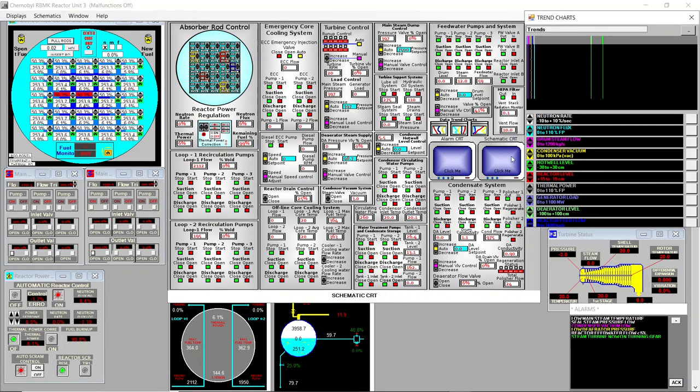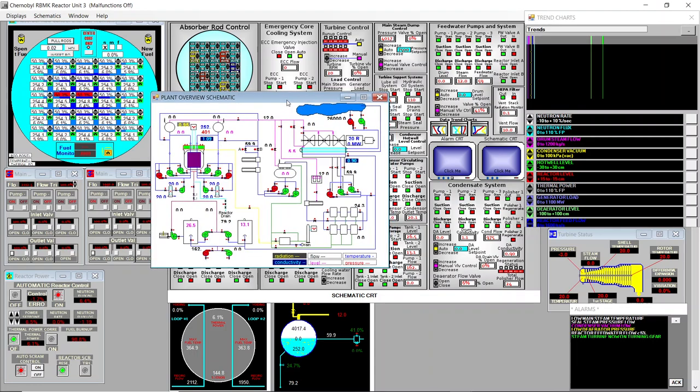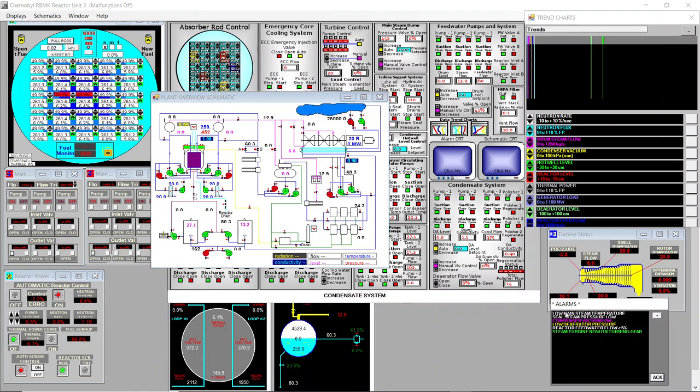a disk rupture. What is a disk rupture? Actually, if you don't patch the ICD file, it causes a disk rupture. You start the simulation with the ruptured disk. This is a mechanical device which is placed between the condenser and the feed water pumps. I don't know exactly where, but it's within this path here. It breaks if the pressure surpasses a given design level, to avoid breaking this line. So if the disk is broken, you cannot start up the reactor. That's why, when in the alarms panel you have the disk rupture problem, in this legacy version of the simulator, you cannot continue the startup.